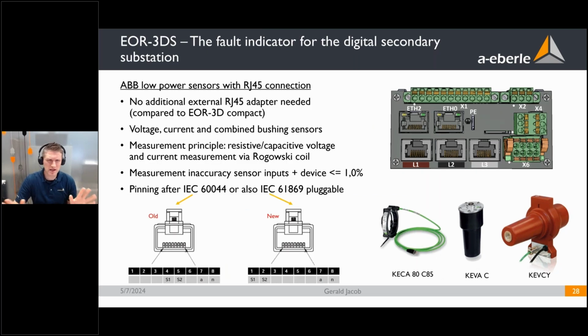Okay, so some very short information about sensors of ABB and Siemens here. The low power sensors from ABB have class 0.5, so the inaccuracy is below 0.5%, and our device itself also has an inaccuracy below 0.5%. So we can guarantee that device plus sensors have an inaccuracy below 1%. That means a measurement accuracy above 99%.